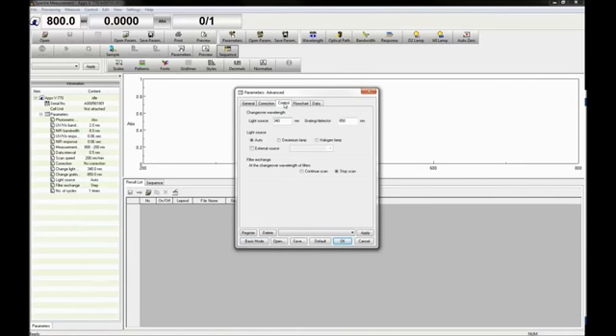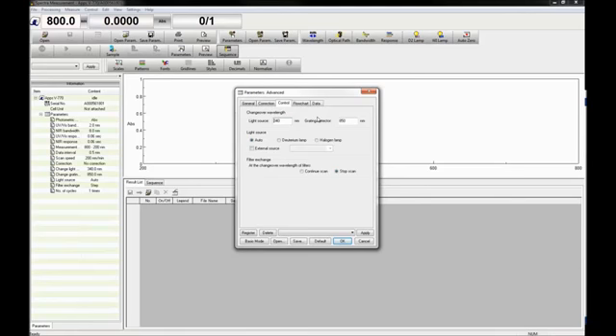In the control tab, you can specify the changeover wavelength for the lamp and for the V770 and V780, the grating detector changeover wavelength. The D2 and tungsten halogen lamps switch at 340 nanometers.